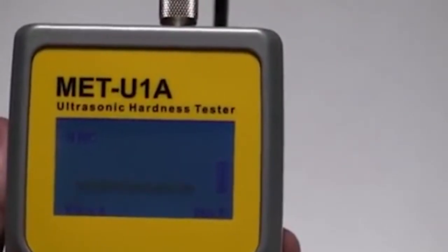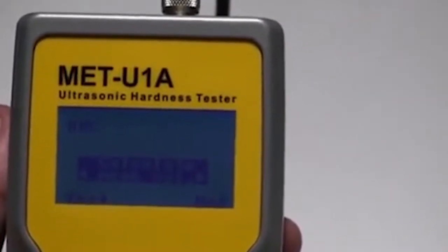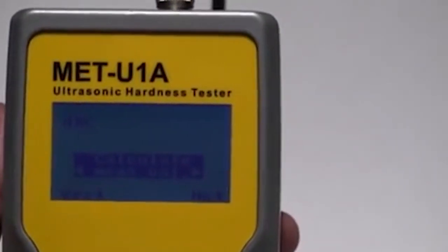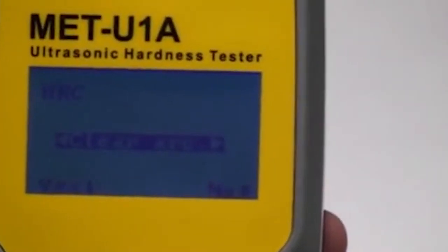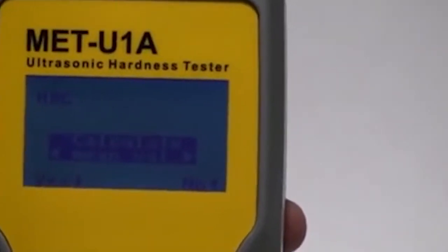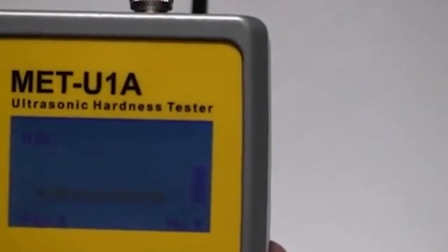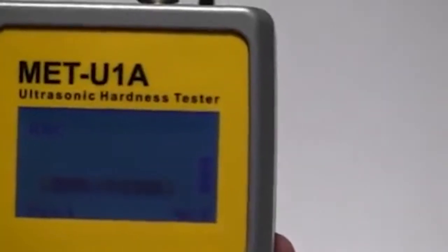Pressing the right arrow button while calibration is blinking will bring you to process. If you hit the down arrow button, you can see it will take you to calculate mean value, or if pressing right or left, clear archives. Pressing the up arrow button anytime brings you back to process in the blinking stage. Scrolling right again using right arrow button brings you to test. While blinking, press on the down arrow button to enter the test mode.